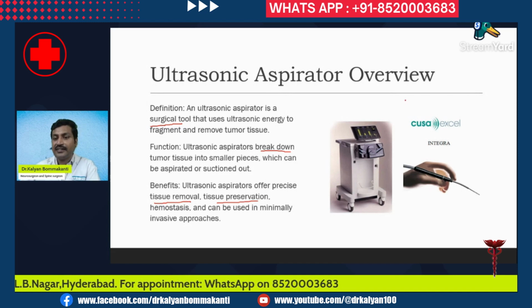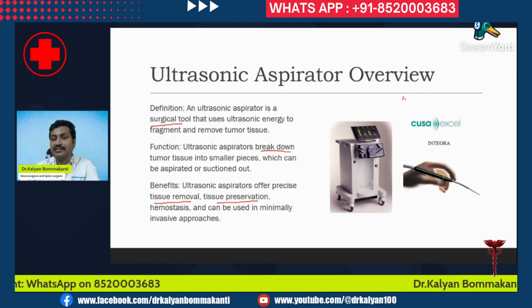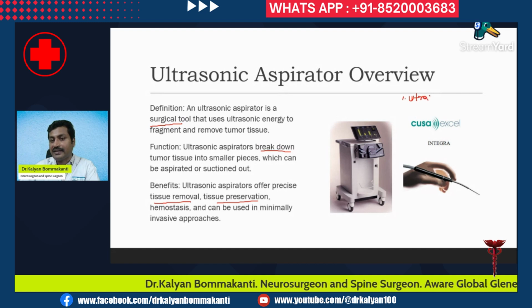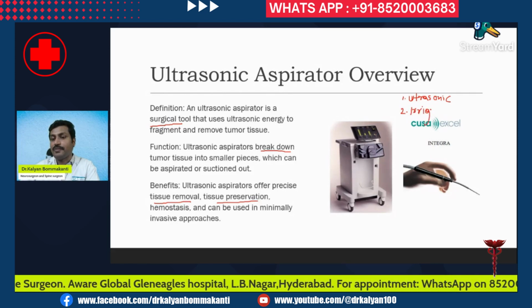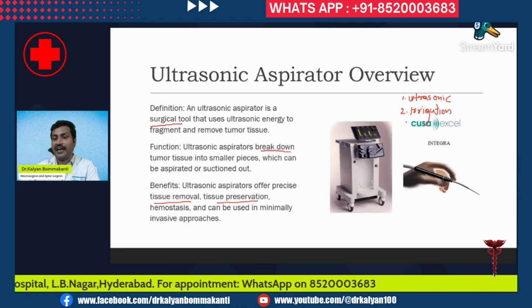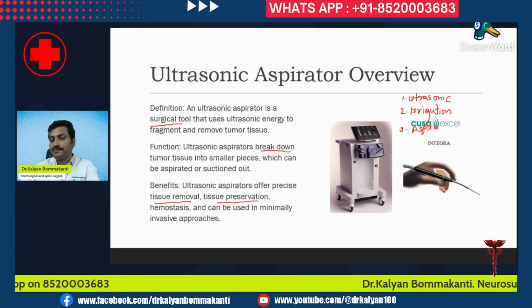Basically, an ultrasonic aspirator is a combination of three surgical things. It has an ultrasonic pulverizer, so there is an ultrasonic material in it. Second, there is an irrigation cannula which continuously irrigates the operative field with saline. And third is an aspiration channel for the small pieces of the tumor.